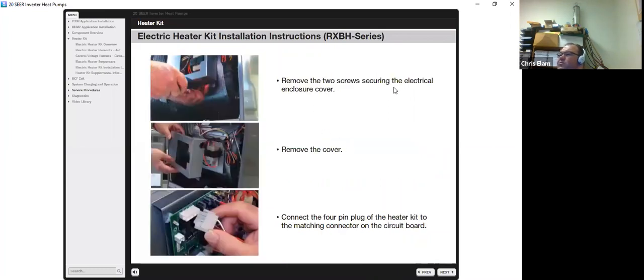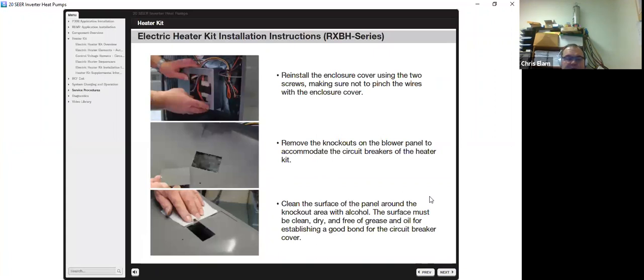Remove the 2 screws securing the electrical cover over the control board. Connect the 4-pin plug of the heater kit to the matching connector on the circuit board. There's only one place for it to go on the board. Reinstall the cover using the 2 screws. Be sure not to pinch the wires with the enclosure cover. Sometimes you have to kind of tuck it through a little bit. There's a little semicircle on the right-hand side that will allow you to route all your wires to the right side and not get pinched down.